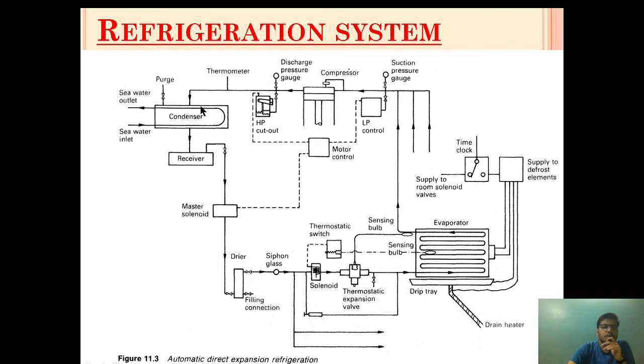More than that, the condenser also serves a purpose of purging out the air present inside the system by this purge valve.